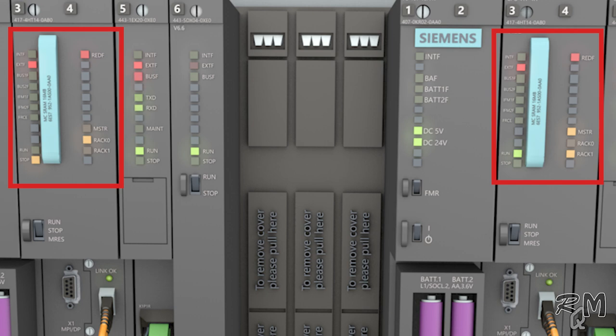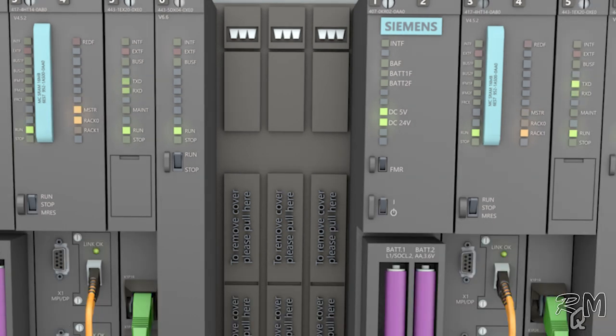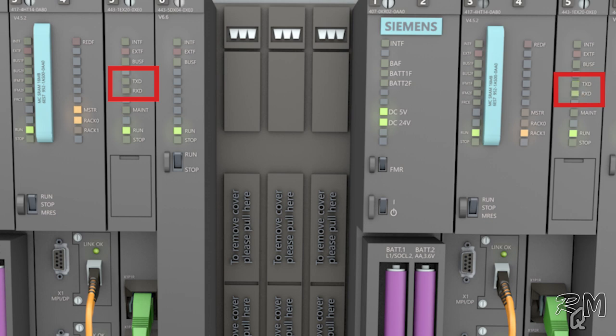Rack 1 CPU remains master even when rack 0 CPU becomes normal. The control will only shift back to rack 0 if rack 1 becomes unavailable due to some fault. In ideal condition all LEDs of both racks are green and TXD and RXD LEDs remain flashing which shows healthy communication.